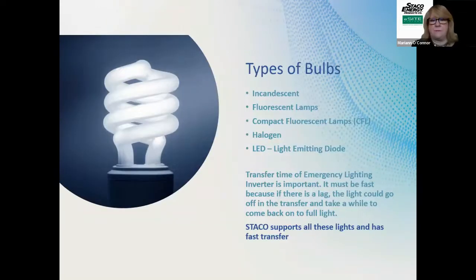There are different types of bulbs out there. We all know incandescent. LED lighting is certainly most of what we see, but there's halogen and fluorescent, and all of our lighting inverters can take care of all of those types of bulbs. And you just need to make sure that the transfer time is fast enough so that any bulb that does dim doesn't take some time to come back once power is coming back to the light. So it's very important to look at the transfer time of the emergency lighting and not have any lags. And the Staco lighting inverters do handle all of those kinds of bulbs. Next slide.